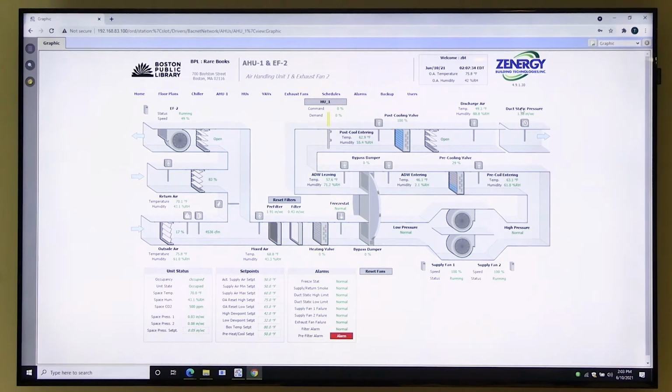Honestly, with this system, it probably won't be a big problem, because if that sensor failed, it would typically fail to 0. The fans would ramp up, which they are already at 100%. So you really wouldn't have a big problem. The typical idea, so I'll go through the basic flow of this unit and what it's trying to do.